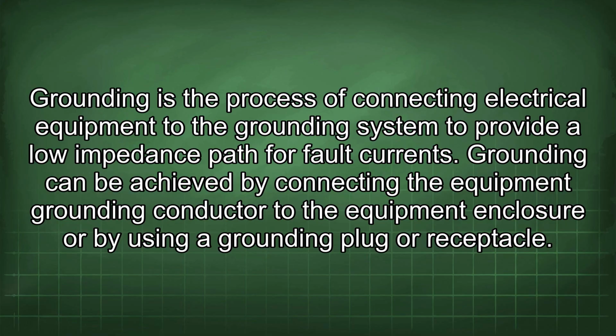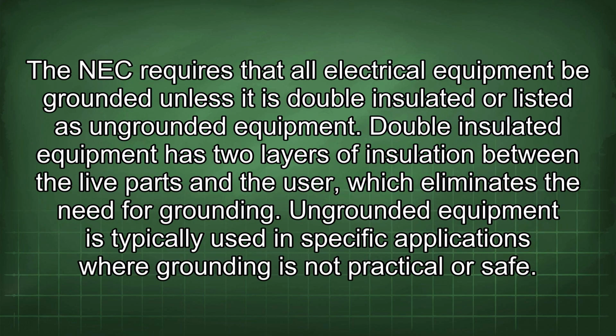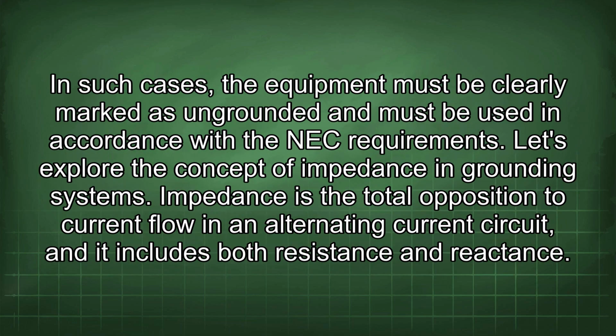The NEC requires that all electrical equipment be grounded unless it is double insulated or listed as ungrounded equipment. Double insulated equipment has 2 layers of insulation between the live parts and the user, which eliminates the need for grounding. Ungrounded equipment is typically used in specific applications where grounding is not practical or safe. In such cases, the equipment must be clearly marked as ungrounded and must be used in accordance with the NEC requirements. Let's explore the concept of impedance in grounding systems.